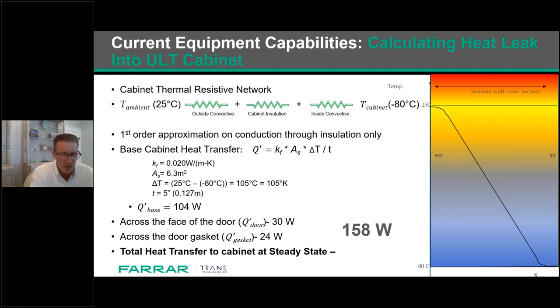So, this is where the insulation is assumed to be equivalent to roughly 5 inches. But in the last 15 years, many manufacturers have gone to what we call VIP, vacuum insulated panel. And the beauty of that is that we don't need a 5-inch wall thickness. The base of the cabinet includes the sides, back, and the bottom. So this is the area, in the middle of the slide, which is roughly equivalent to 6.3 square meters. The same calculation applies across the face and the door gasket. The only change is the surface area.